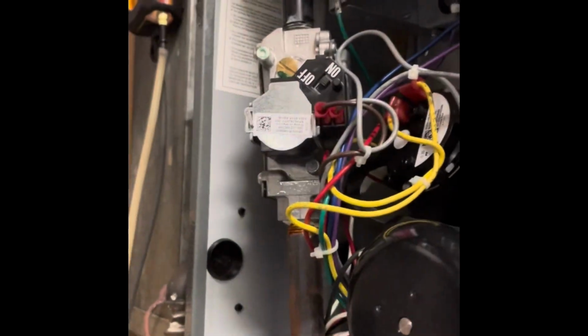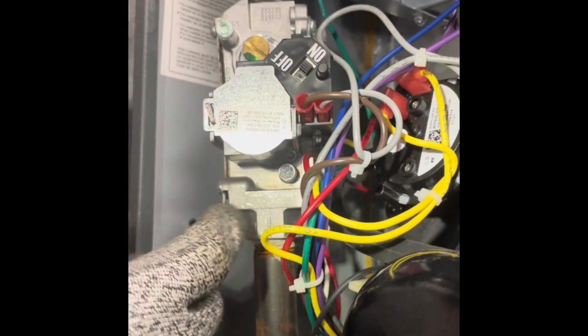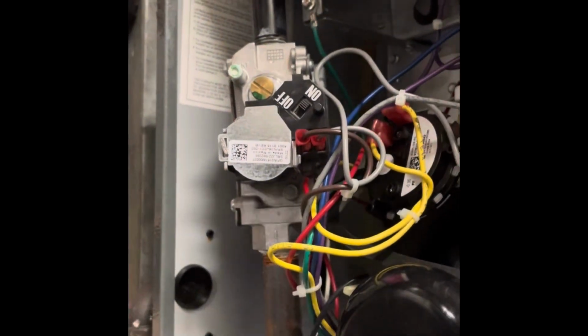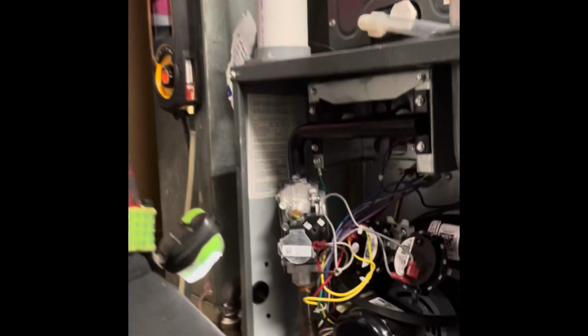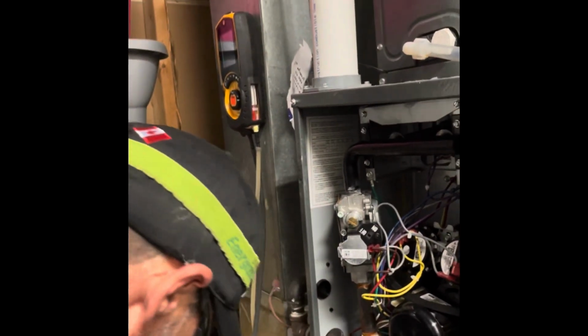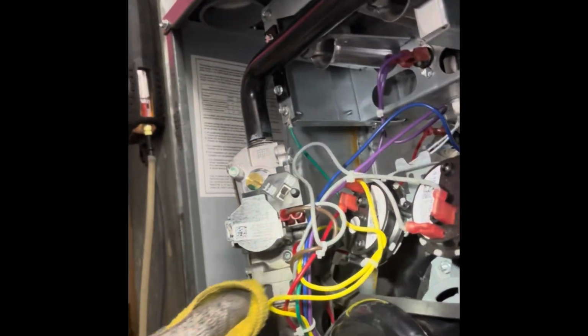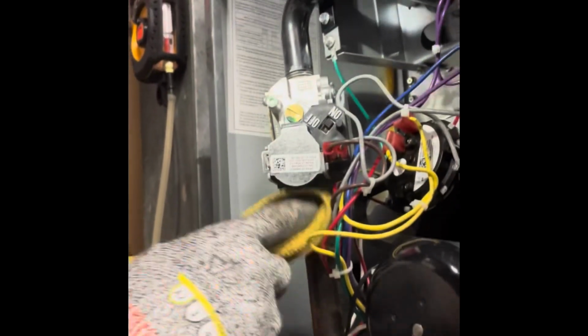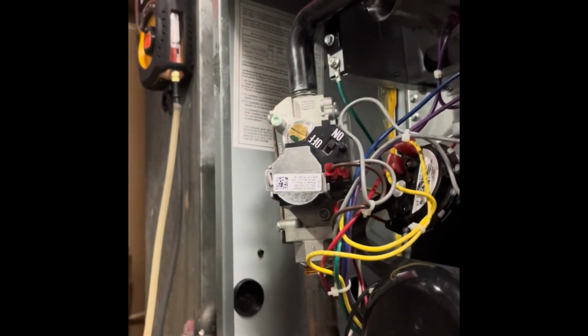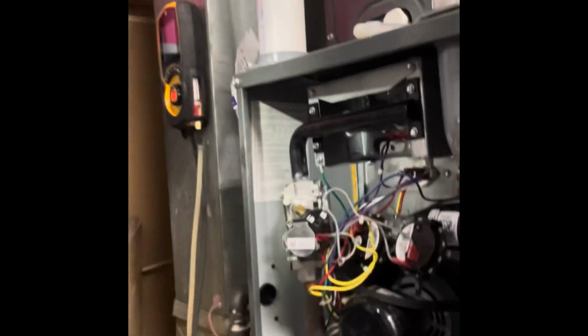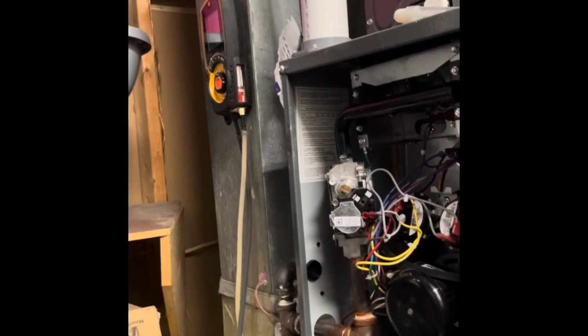And then just give me an indication to tighten it more to get that leak to stop. So as you guys can see, none of these bubbles are moving. I've got nothing blowing up, which indicates that there's no leak at that port. Now what I'm going to do, you always want to dry up the soap, because if you don't, you're going to get a lot of calcium and stuff building up along that valve, and that could mess up the little washer that's in there.